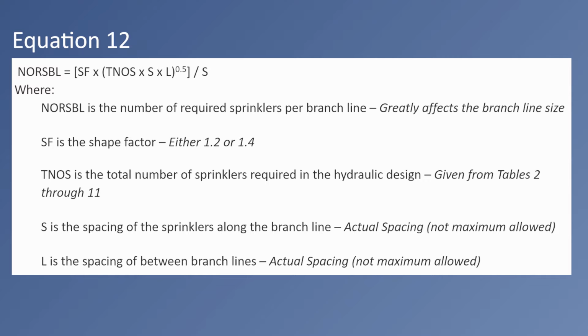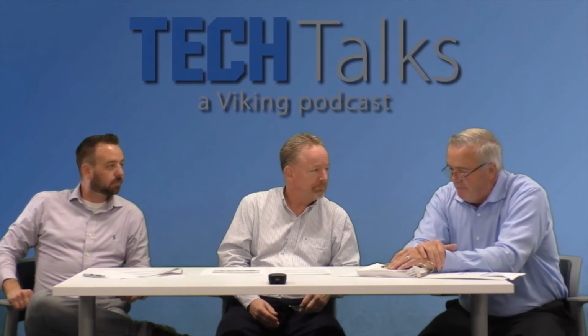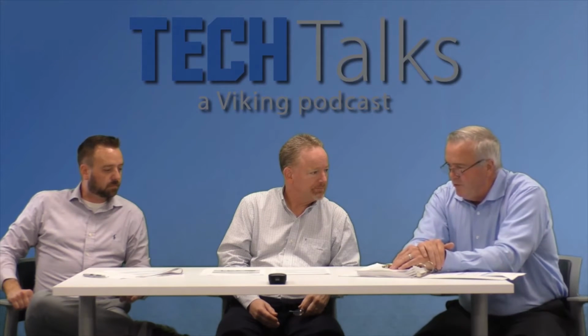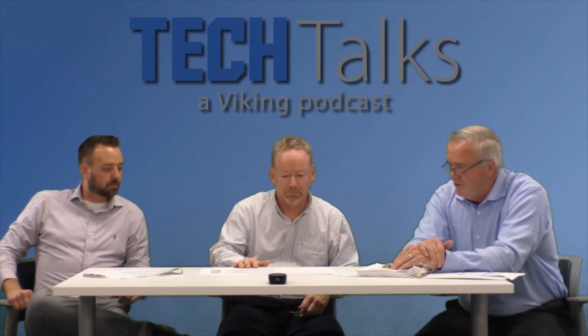You went through the appropriate standards and the time frame, but every once in a while, an old dog can learn new tricks. You know, I've spent a career of knowing storage and teaching storage, and the 4 sprinklers on 3 branch lines was like a default. You just knew it. That's what it is in NFPA 13. By the time you do the formula for 12 sprinklers, in most spacing applications, it is 4 sprinklers on 3 branch lines.